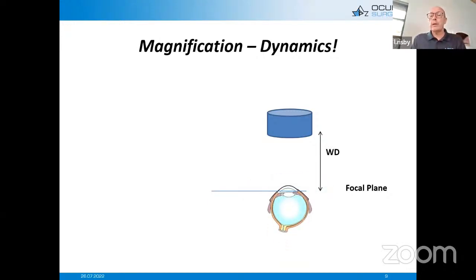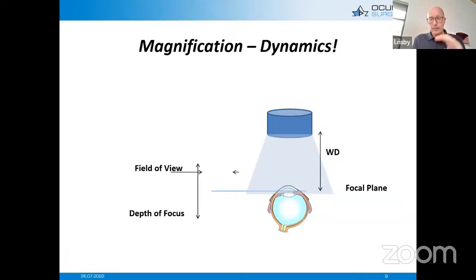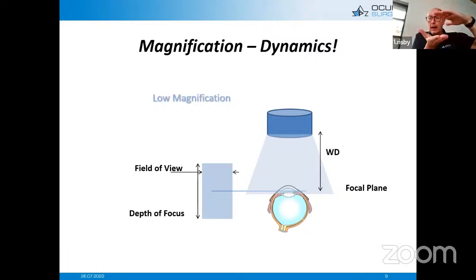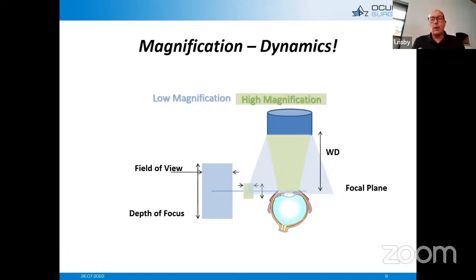We want to bring the focal plane down to the limbus. At any given magnification, we have a field of view and a depth of focus. At low magnification, the depth of focus is very high and field of view is wide, whereas at high magnification, we have a very shallow depth of focus and a narrow field of view. This is the reason why sometimes, if you zoom in with a microscope, you will go out of focus — and I will get back to this.